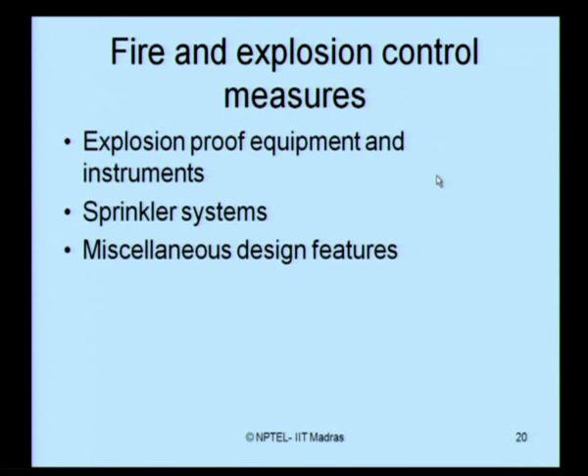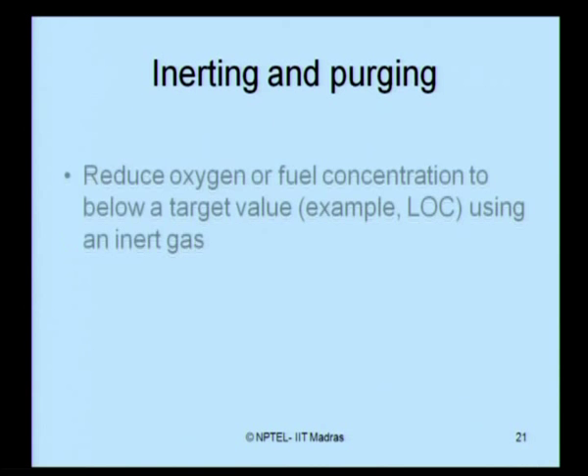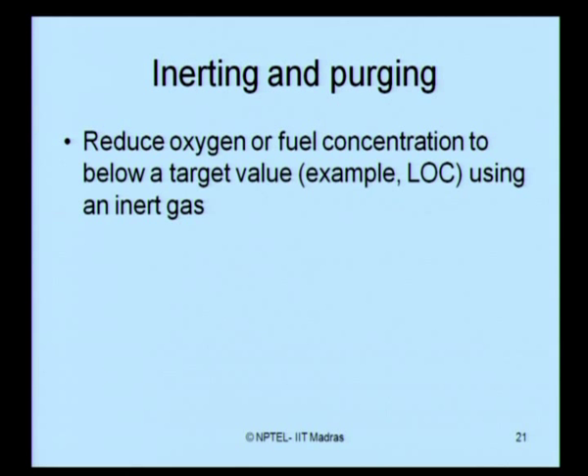For fire and explosion control measures, you can also use explosion-proof equipment and instruments, sprinkler systems, and other miscellaneous design features. Let us look at inerting and purging in detail. Our target is to reduce the scenario that can cause explosion or fire. Inerting or purging is a process where you reduce oxygen or fuel concentration to a level below a target value, such as the limiting oxygen concentration — the minimum oxygen content required to cause combustion for a mixture.